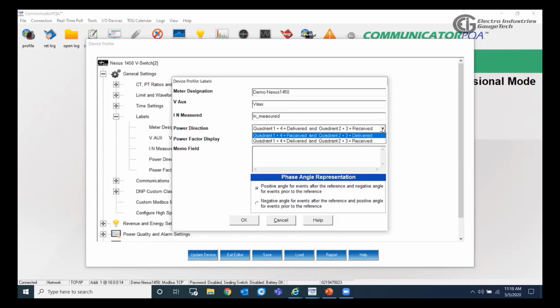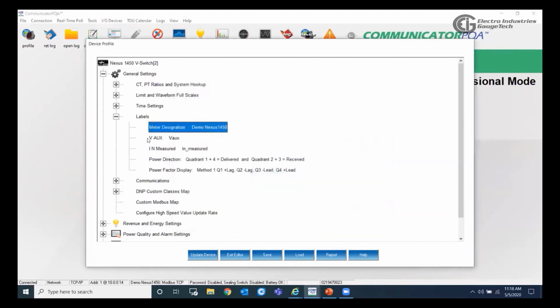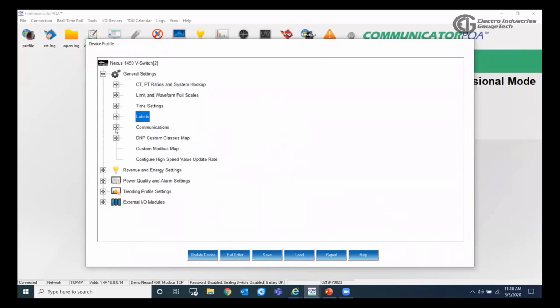That is, is the energy delivered to the customer, or is it received? Most of the time, when the meter is installed at the customer side, we consider that delivered energy to the customer. When we are using the meter on a generator, for example, we would be looking at received energy from the generator. We also have a power factor display with method 1 and method 2, and that will give you either the sign for the power factor or the 4 segments in the different quadrants. Then we will hit OK and go to the communications.